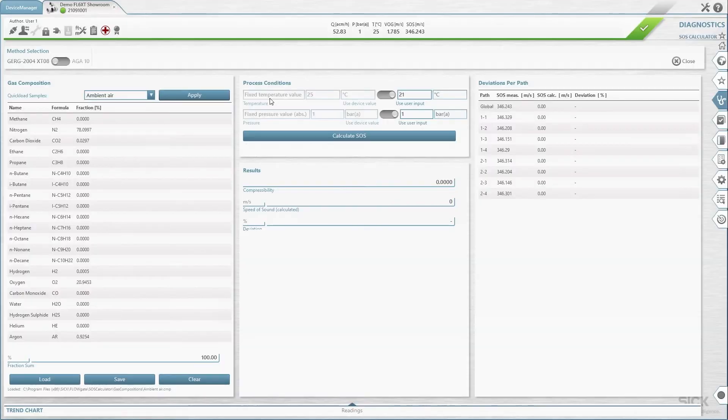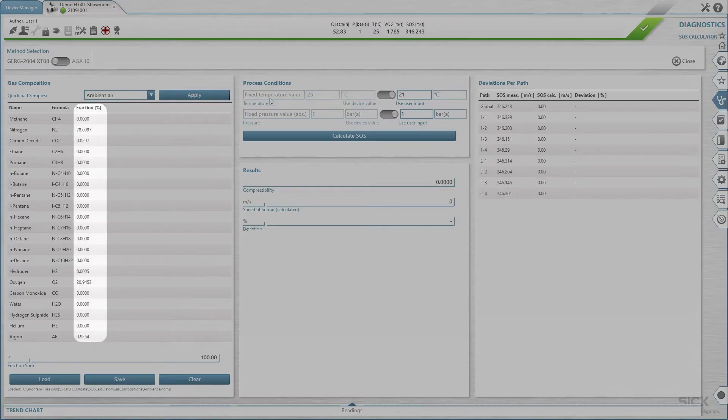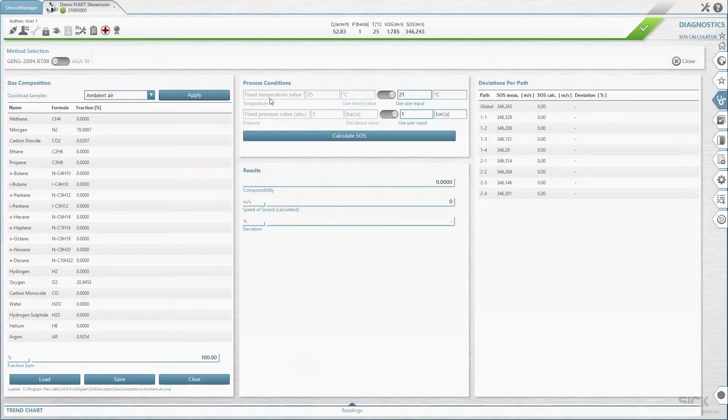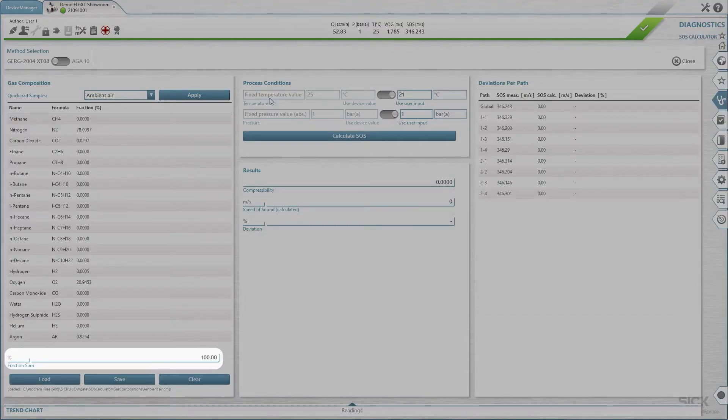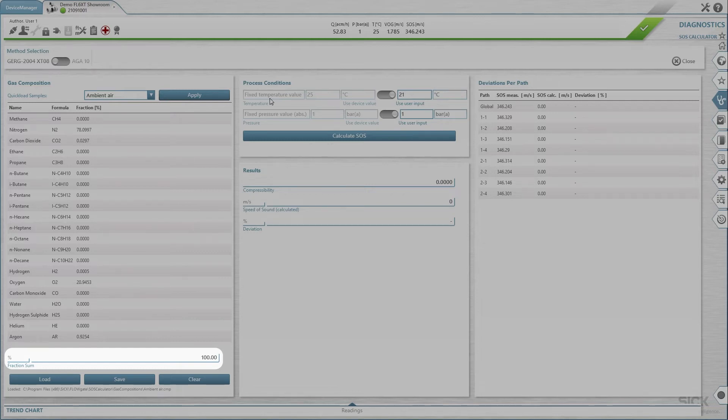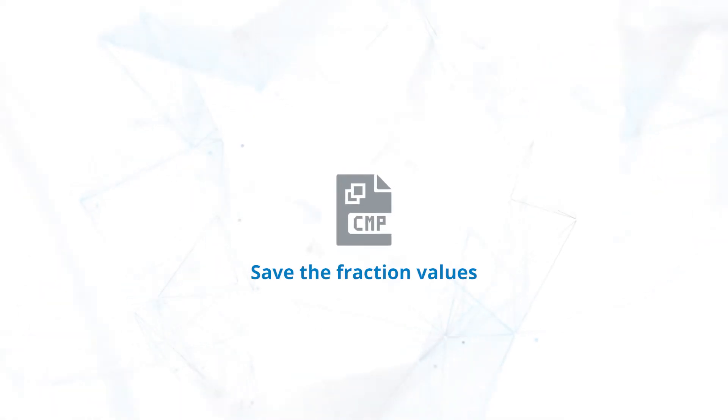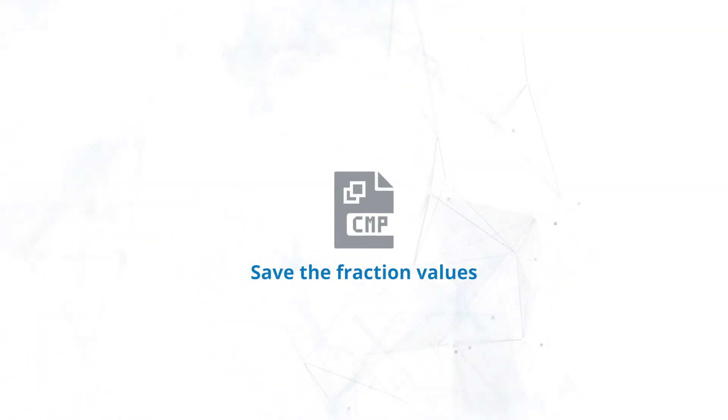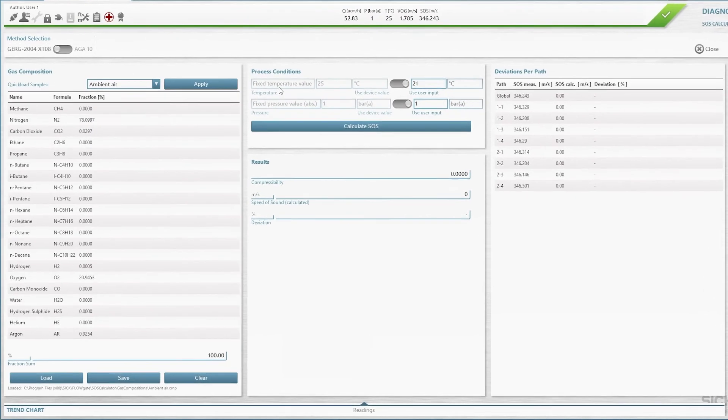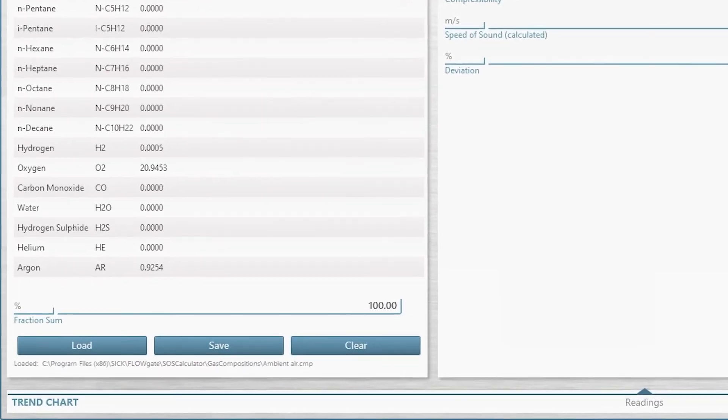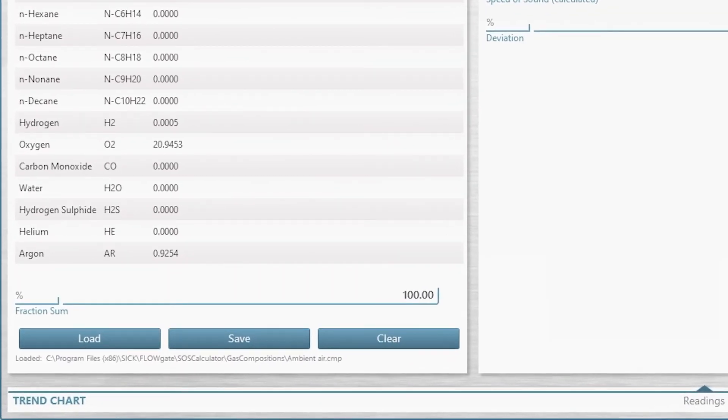To modify or define a custom gas composition, modify the component fraction in terms of percent in the column Fraction in Percentage. To apply the modified gas composition to the speed of sound calculation, the fraction sum at the end of the list must be between 95% and 105%. After you have entered the gas composition, you can save the fraction values together with the temperature and pressure values as a file with the extension CMP. Use the load, save and clear buttons for this purpose.